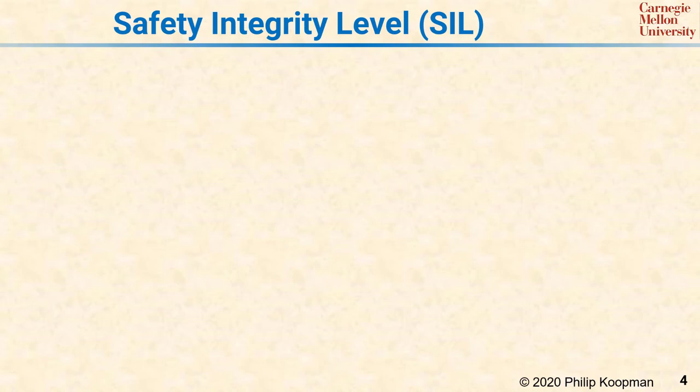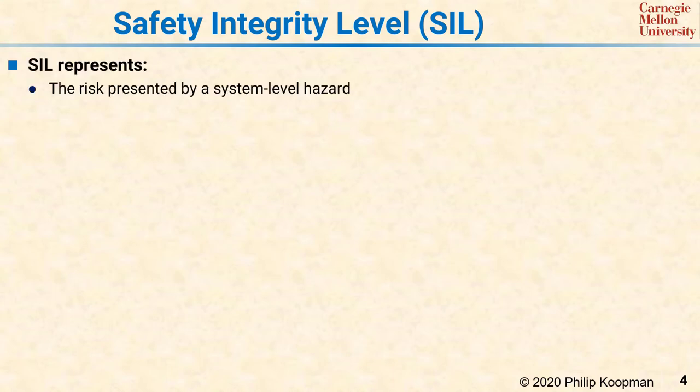The general strategy for building critical systems is to first define a Safety Integrity Level, or SIL, that is required and then use that SIL to guide the system design process. In practice, a SIL represents three related things. First, it represents the risk presented by a system level hazard, with a high SIL being considered extremely hazardous and a low SIL considered minimally hazardous.